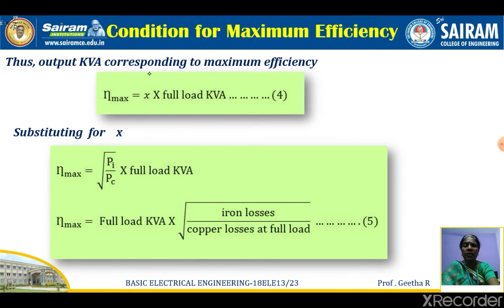Thus the output kVA corresponding to the maximum efficiency is that fraction X into the full load kVA. Output kVA corresponding to maximum efficiency is that fraction into the full load kVA. When you substitute for X, it is the square root of Pi by Pc into full load kVA. So the output kVA at maximum efficiency is equal to full load kVA into square root of Pi by Pc, where Pi is the iron loss and Pc is the copper loss at full load.